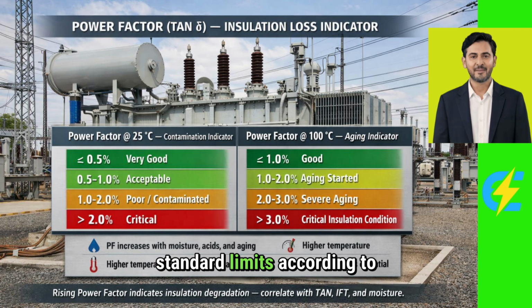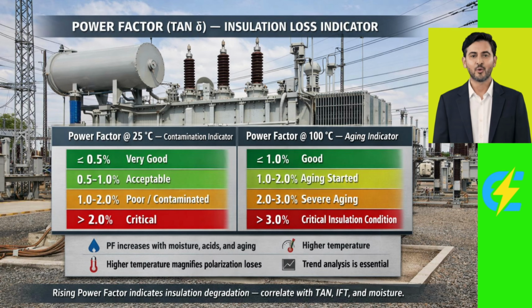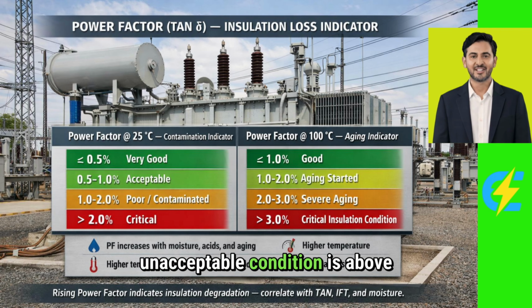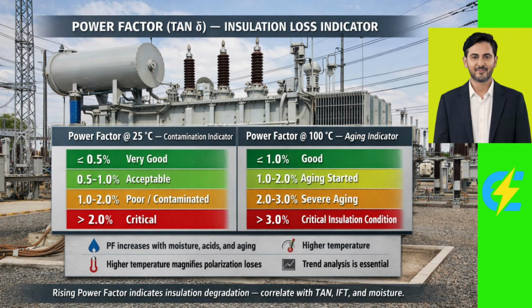Let's look at the standard limits according to IEC 60422. For power factor at 25 degrees Celsius, good condition is below 0.005. Caution zone is between 0.005 and 0.01. And poor condition is above 0.01. For power factor at 100 degrees Celsius, good condition is below 0.02, caution zone is between 0.02 and 0.05, and unacceptable condition is above 0.05.